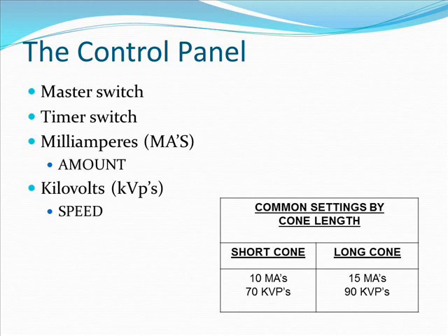In the olden days, x-ray heads, and I never worked on one, but x-ray heads used to not have an automatic cutoff switch. So you would have to push the button for the right amount of time and release it at the right amount of time in order to stop the radiation. They can't make them that way anymore. It's a regulation that they have to have an automatic cutoff switch.